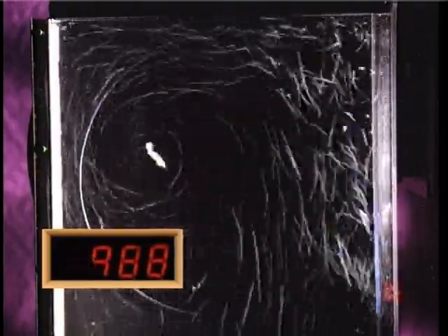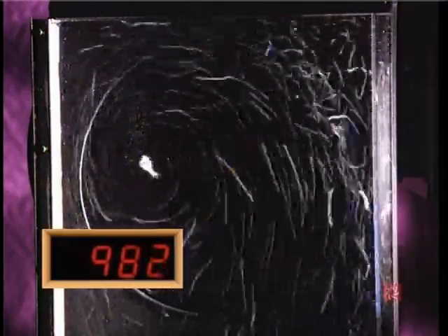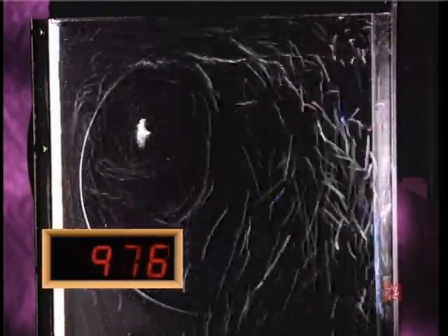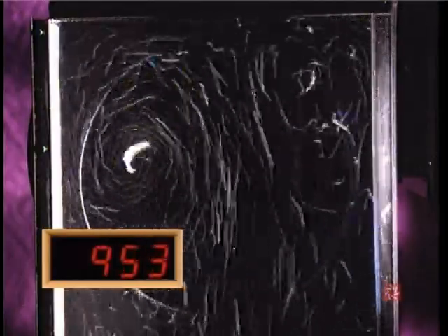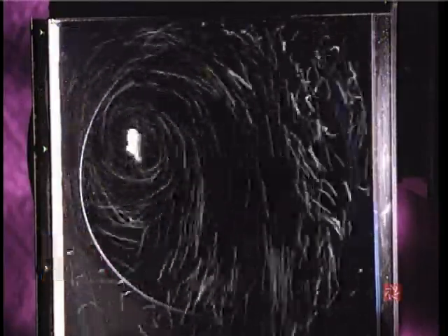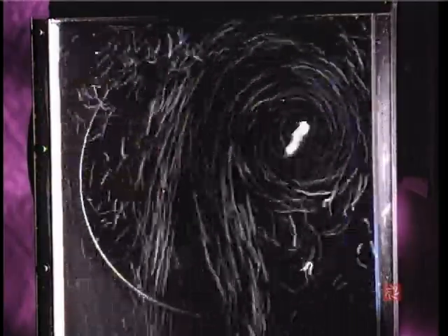Non-uniform flow into the inlet is the most common cause of reduced fan performance. These conditions alter the aerodynamic characteristics of the fan so that its full airflow potential is not realized. Listen to the pulsating sound of the fan. Notice that the fan is hunting, trying to find a stable operating point.